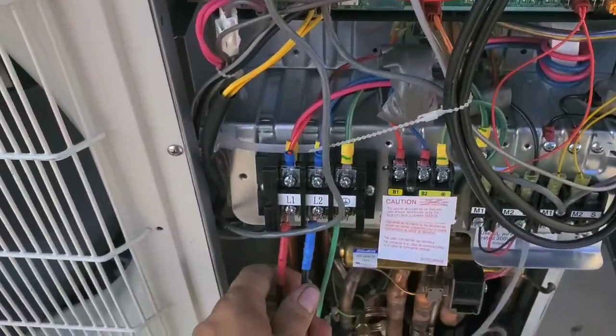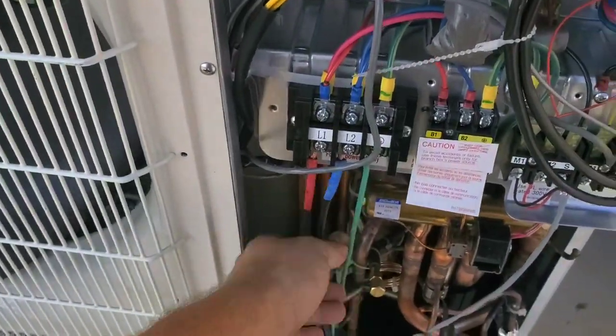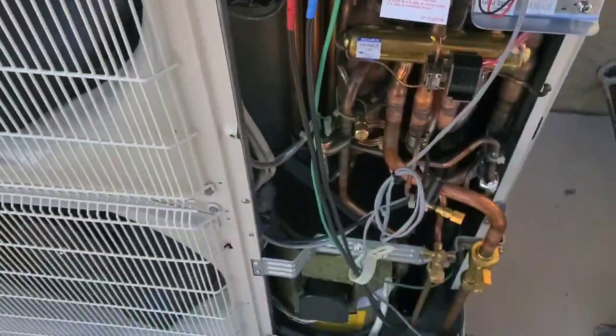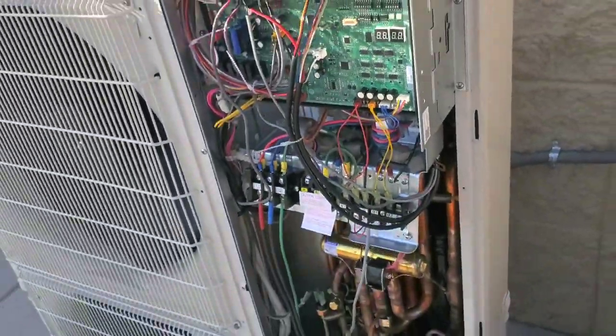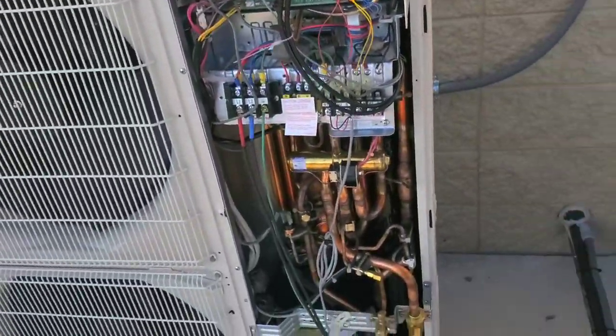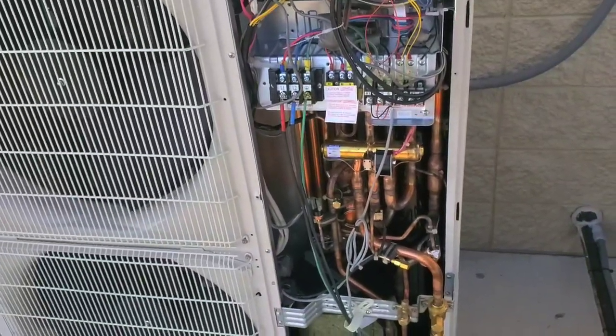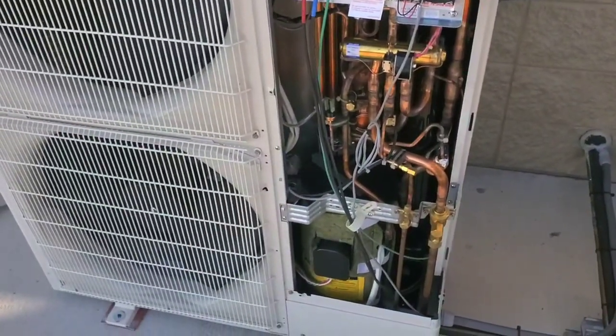So now that I've tightened these connections that the electricians neglected to tighten, I'm supposed to put power to it and leave it for 12 hours because there's no crankcase heater and it pulses power through the windings of the compressor to warm it up.